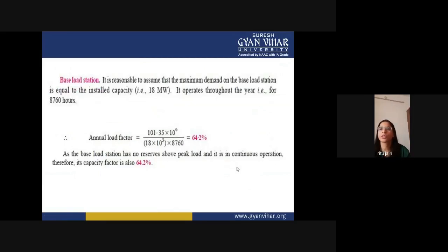Now we come to the base load station. It is reasonable to assume that the maximum demand on the base load station is equal to the installed capacity, which is your 18 megawatt, because it will continuously supply the load, which is 18 megawatt. So it operates throughout the year for 8760 hours. I have already discussed what is base load and what is peak load. Base load is that which is continuously supplied to the consumer throughout the year. It can't be more than your 18 megawatts. So the maximum capacity, or you can say the maximum demand, of this base load station is your 18 megawatt, and one unit is always standby. When you require maximum demand, then you can use that particular standby unit.